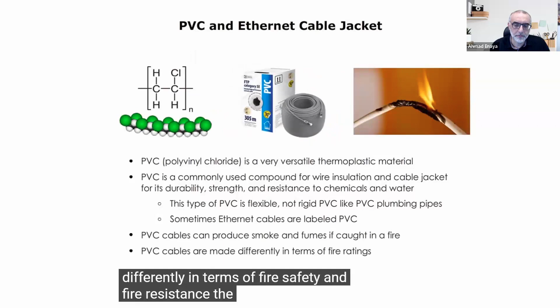So we have 3 ratings: CM, CMR, and CMP. Which one is the general purpose one? This one, CM. Which one is designed for the riser, between floors? CMR, the R stands for riser. Which one is designed for plenum? CMP. The name is clear because the last letter mentions the location where this should be installed.